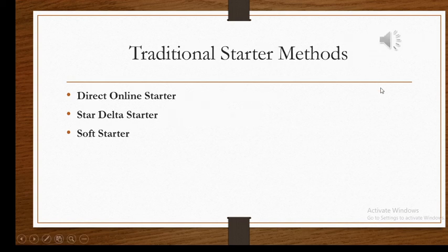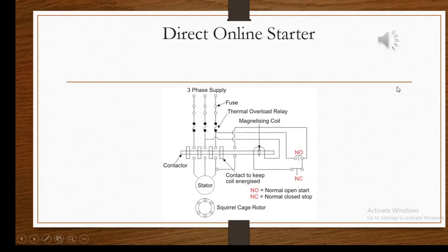Some of the traditional starter methods for induction motor are direct online starter, star delta starter, and soft starter. The basic components of a direct online starter are a circuit breaker, a contactor, and an overload relay. When the starting current consumed by the motor is overloaded such that it's above a certain threshold, then the overload relay of the direct online starter is activated, due to which the supply to the motor breaks and hence the motor comes to rest. This helps the motor to avoid damage due to excessive current.